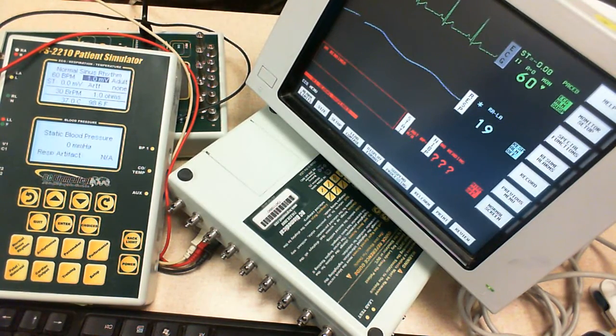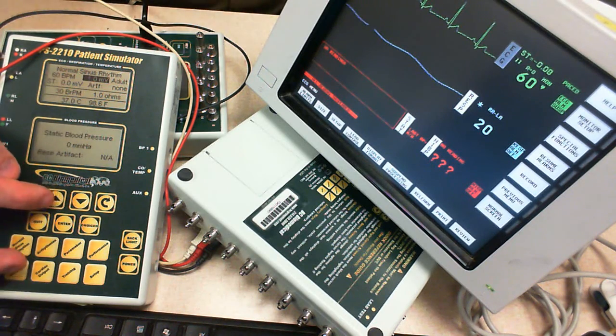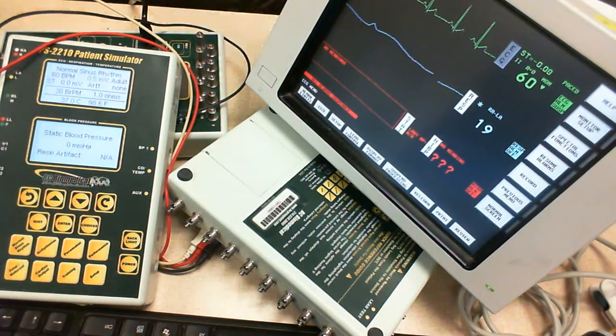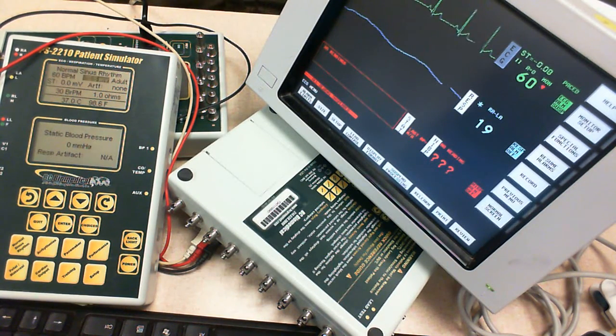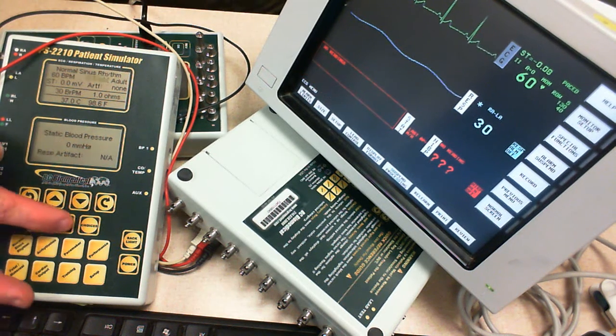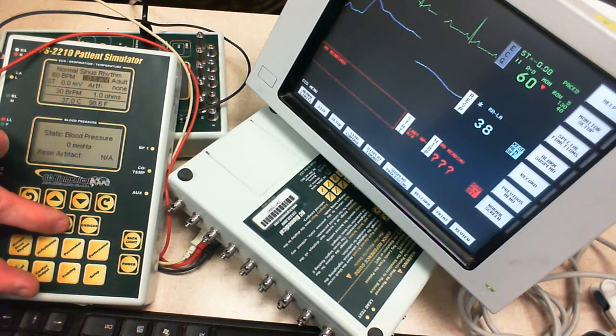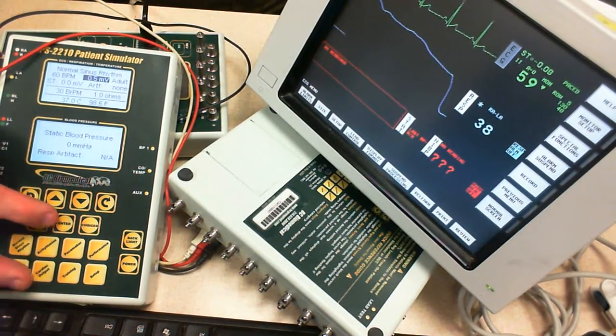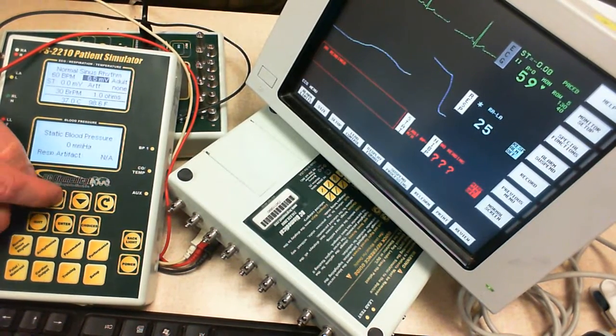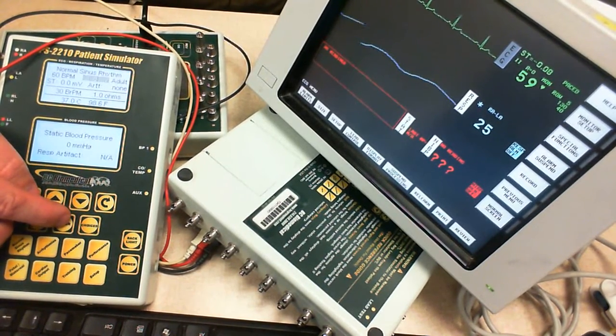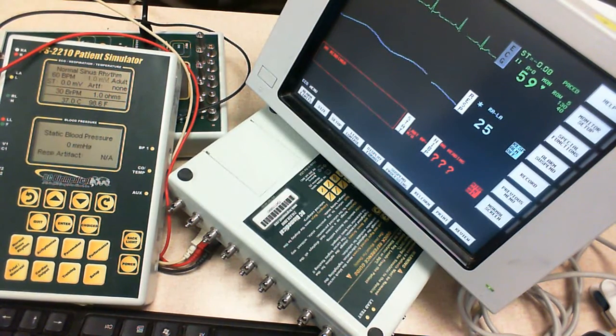What we're going to do now is a gain check. I want to change it from 1 millivolt to half a millivolt. You can, by the way, do this with 1 millivolt to 2 millivolt. What should happen to the approximate size on the screen when I cut the voltage in half? It should drop approximately in half. Let's see if we can catch this on the screen. See that one? Oh, I didn't. Took a little bit of time. Notice there it's approximately half the size as it was before.